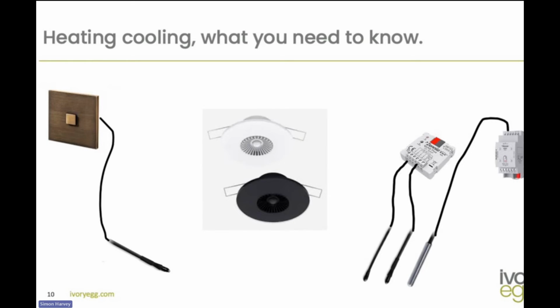Of course, there are switches that don't have any temperature reference or ability at all. But interestingly, a lot of the new switches, and in particular the Lithos switch, have the ability to take in an external probe in the back, an NTC probe. That probe can sit underneath the floor or in the concrete, or come from somewhere in the hydronic system, and it can send the temperature, calculated and scaled within the switch, out onto the KNX bus to a thermostat logic sitting somewhere else. The Lithos switch also has thermostat logic built in, so we can use either for temperatures.